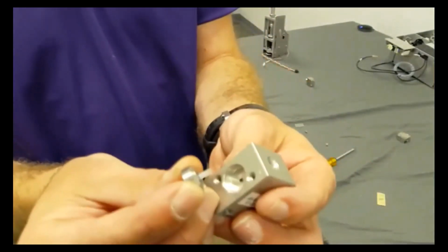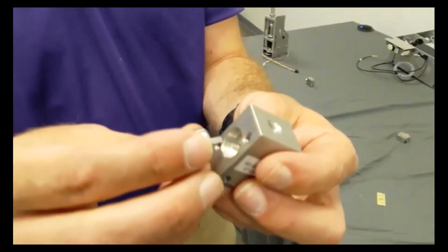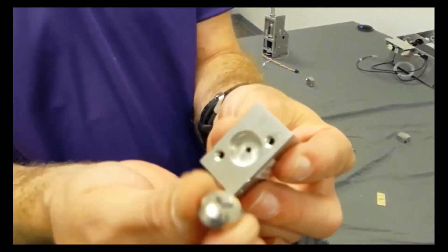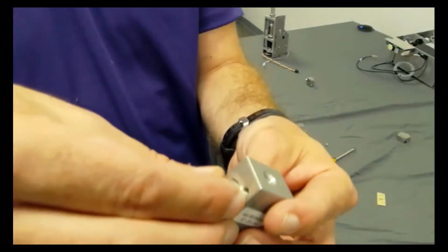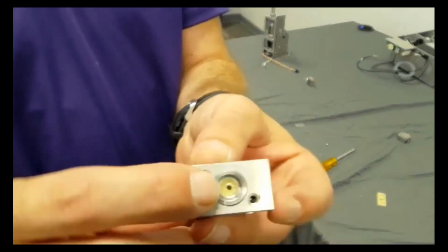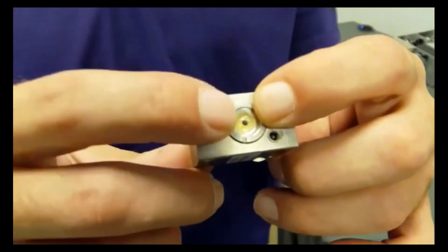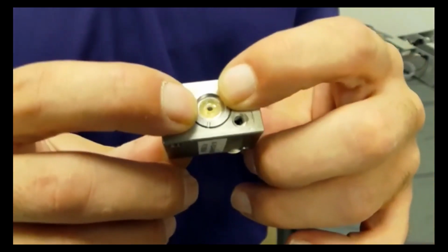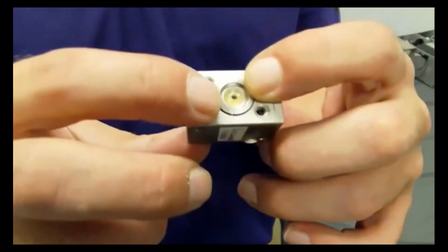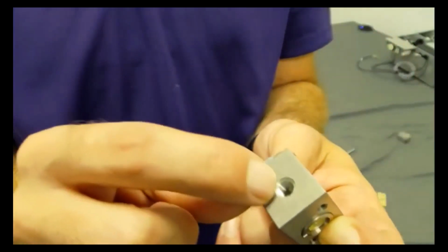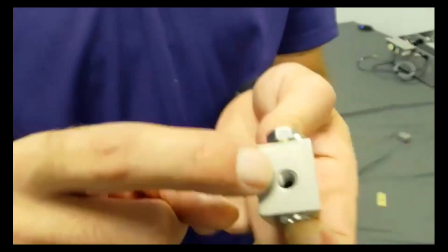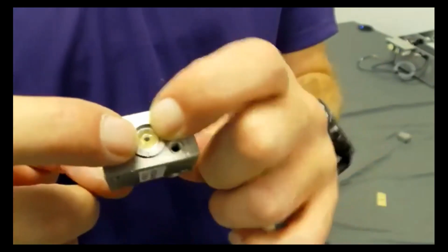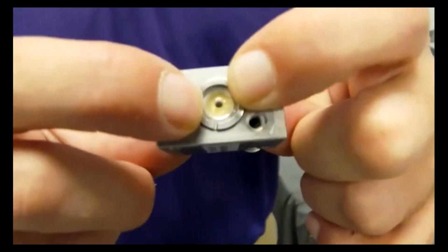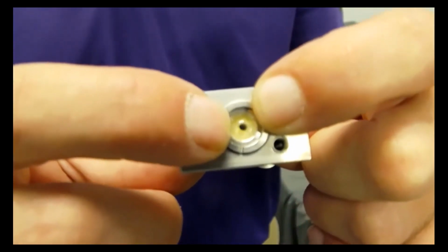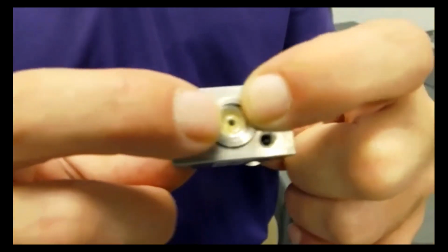Now, putting these back, you want to be gentle, okay? Do not be in a rush to do this, but you'll find the hole down in there that the quartz rod goes in. There you go. Now, another reason why we say not to sonicate is because that's glue right there. And this glue can become gummy and malleable again in certain solvents that we recommend for flushing out in here. This glue is only on this side. So if you flush the flow cell out through the unit, this glue will never touch that solvent. But methanol and acetone will probably break this glue down. So this is another reason why we say don't sonicate the flow cell if you can help it.